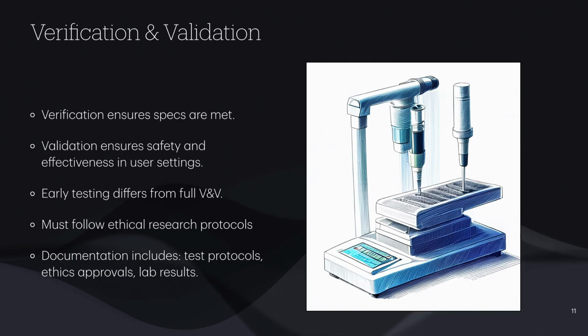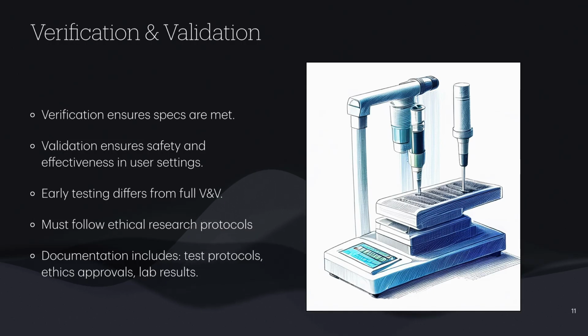Verification involves bench testing in simulated environments, mechanical stress analysis, tolerance checks for components, and electrical safety testing. Validation includes clinical trials or observational studies, usability assessments with real clinicians, and field testing in hospitals. These tests are not optional. They are part of your risk management file, your design history file, and your regulatory submission package. All validation involving humans require Ethics Review Board or ERB approval. For high-risk devices, this can be extensive.